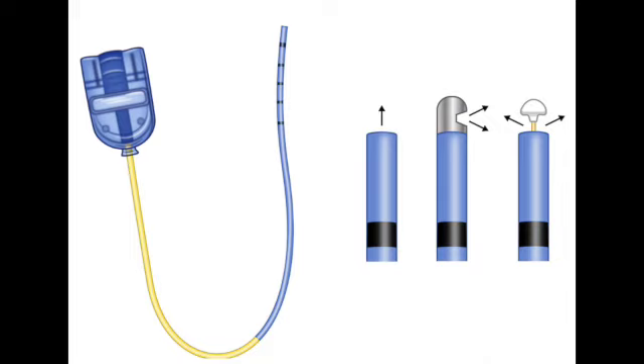Now, let's nail down this duration factor. You mentioned watts, flow, and duration. Why is holding the pedal down longer potentially more dangerous than just cranking up the watts a bit? It comes down to total energy delivered, which we measure in joules. Energy equals power multiplied by time. So let's say you're using 45 watts. If you apply that for just 1 second, you've delivered 45 joules of energy. But if you keep your foot down for 3 seconds, same power, 45 watts, you've now delivered 135 joules. Triple the energy. Triple the total energy, and that extra energy doesn't just stay on the surface, it penetrates deeper into the tissue. That's where the real danger lies, deeper thermal injury.